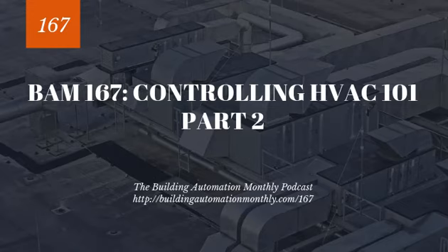So you've got pressure safeties. Those are going to measure high and low static, so that'll make sure your fan doesn't blow out or suck in ductwork. You have contact safeties. These can be anything from damper position contacts. Dampers are the main ones that I used contact safeties for back when I was in the field. So I'd make sure I had a damper status.